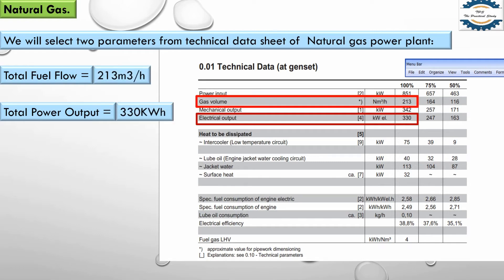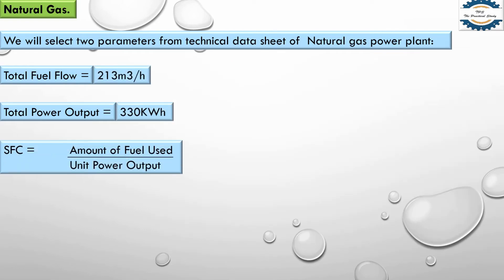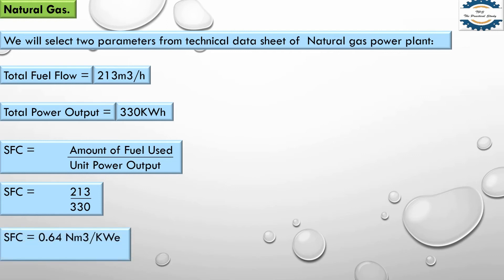Putting these two parameters into the formula, specific fuel consumption equals amount of fuel used divided by power output. Fuel use is 213 cubic meters per hour and power output is 330 kilowatt, giving us 0.64 cubic meters per kilowatt. So to produce one kilowatt of electricity from a natural gas power plant, 0.64 cubic meters of natural gas is required.